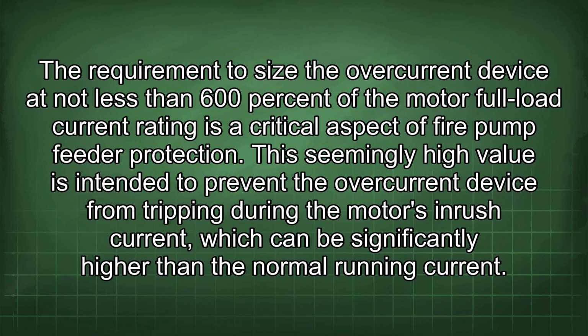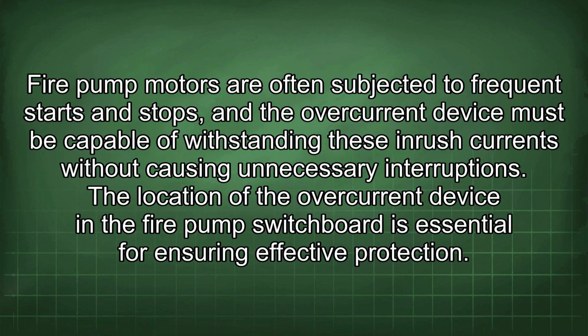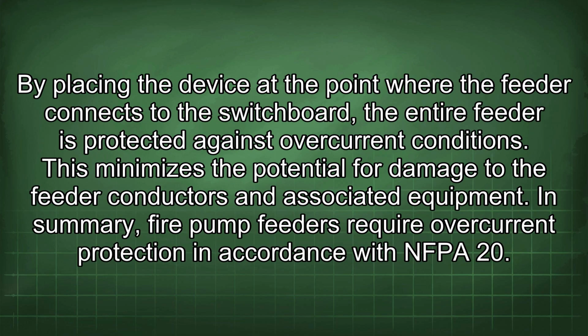This seemingly high value is intended to prevent the overcurrent device from tripping during the motor's inrush current, which can be significantly higher than the normal running current. Fire pump motors are often subjected to frequent starts and stops, and the overcurrent device must be capable of withstanding these inrush currents without causing unnecessary interruptions. The location of the overcurrent device in the fire pump switchboard is essential for ensuring effective protection. By placing the device at the point where the feeder connects to the switchboard, the entire feeder is protected against overcurrent conditions. This minimizes the potential for damage to the feeder conductors and associated equipment.